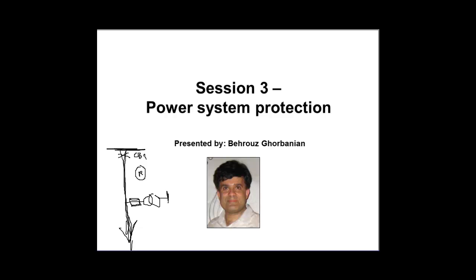This relay will command this circuit breaker by sending a tripping signal to it. However, you need to have input to this relay, and that input is coming from a CT, which is a current transformer. Also, on many occasions, you need a voltage input, and that is what we call the VT, or voltage transformer, again connected to this relay.